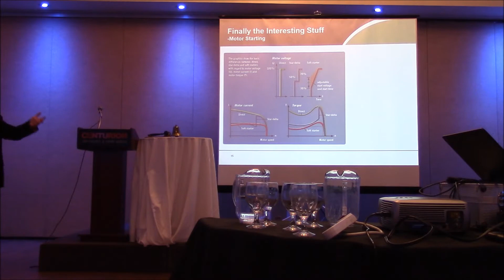If you're coming and talking to me about, well, we want to run the domestic water booster pump, and it's 50 horsepower, and I've got a 1,000 horsepower generator, the code issues to one side, I'm probably not going to have a problem with that. But if you're coming and talking to me about the chiller, which when the chiller is operating, it needs all these other pumps running with it, and its aggregate load of 700 horsepower, 750 horsepower, my 1,000 horsepower generator is not going to get that turning without some very special scheduling of equipment, starting motor loads one after another.